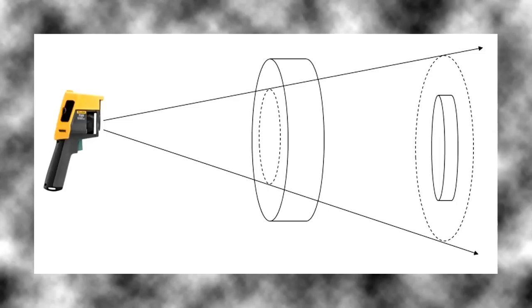In the second case, the target is smaller than the spot size, and any temperatures in that area will be averaged in with the temperature of the target.